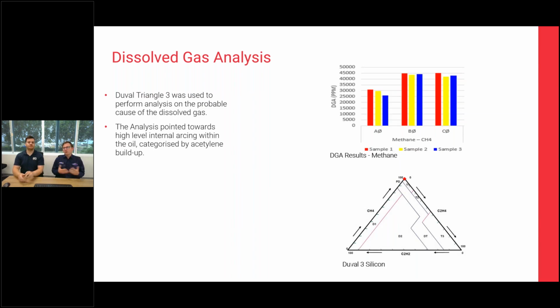So the main way dissolved gas analysis within Powerlink is analysed is the Duval triangles. There are several other methods of ratios in gas that help identify what could be the probable cause. With this particular asset, Duval triangle 3 was first used, and then a separate triangle for silicon synthetic oils was used in further analysis. What we can see is the ratios clearly point to high energy internal arcing and discharge, commonly referred to as PD. So we were fairly confident that there was partial discharge occurring in the asset. The DGA combined with the phase plot analysis and the pulses per cycle and the information and support we got from EA, there was a high level of confidence that we had issues inside these HV terminations.